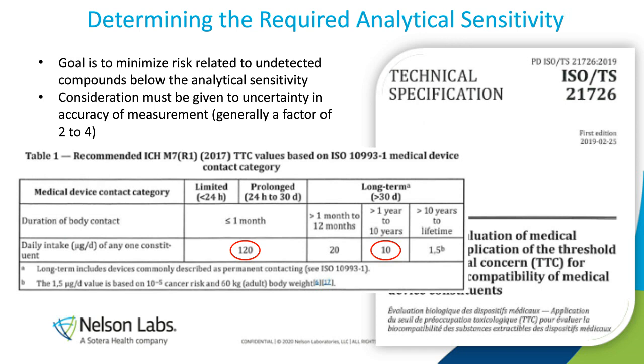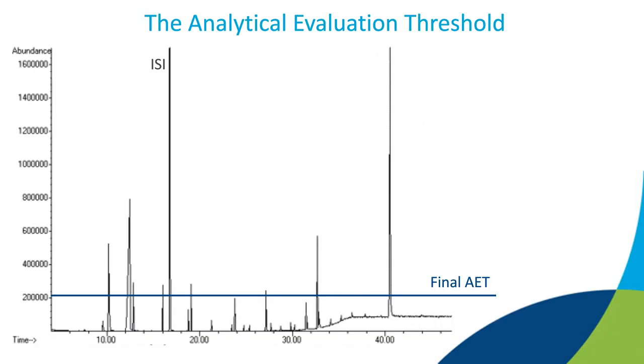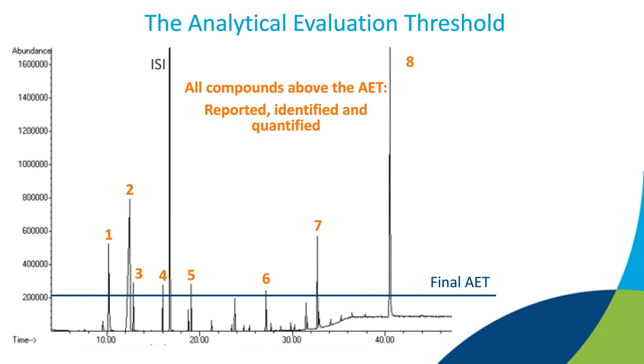And so this analytical evaluation threshold, like I said, is core to this whole conversation. It's a little bit new in the sense that within the last 6 months, this articulation of what the analytical evaluation threshold is and how it is applied, I really see that as an absolute requirement for submission to the FDA at this point. So if you don't articulate that, then you can expect a question and delays related to that.